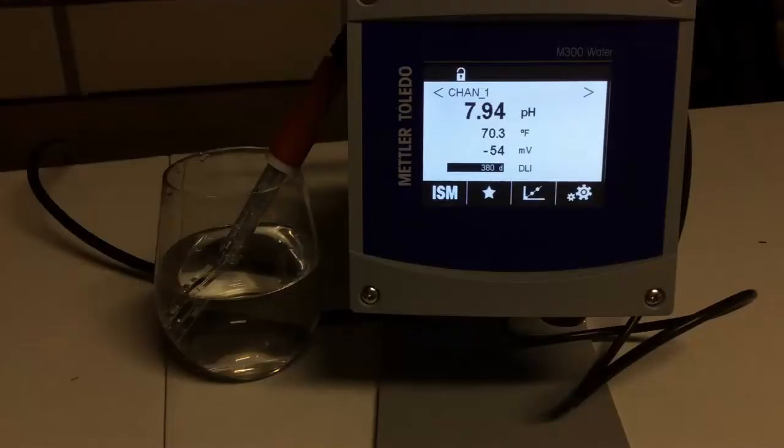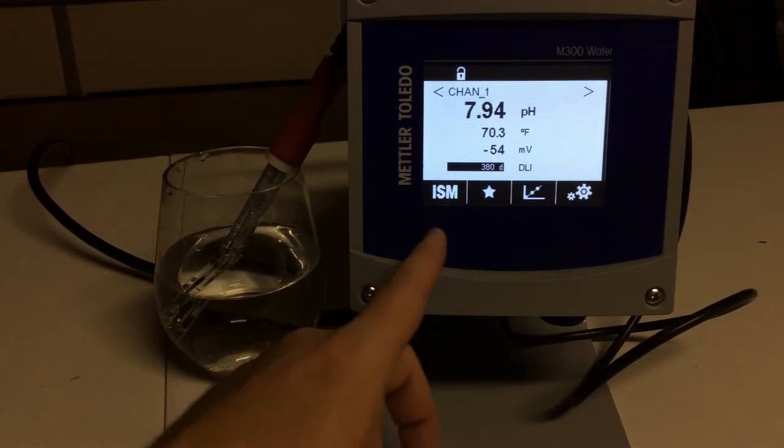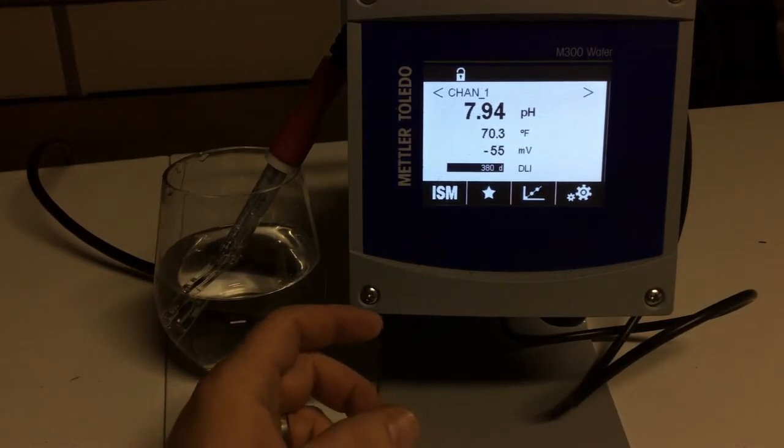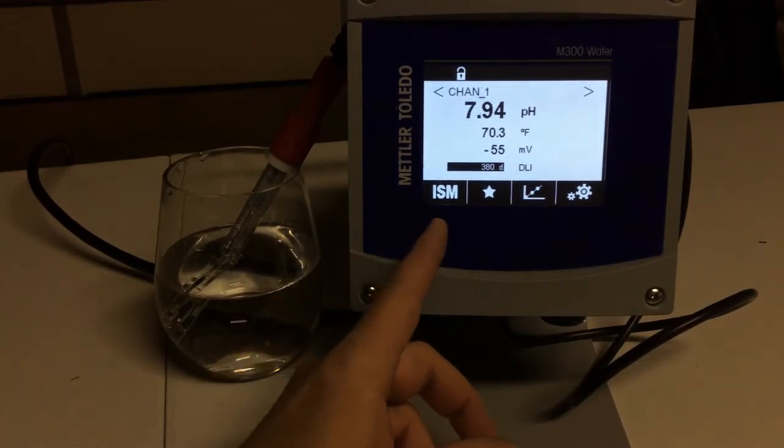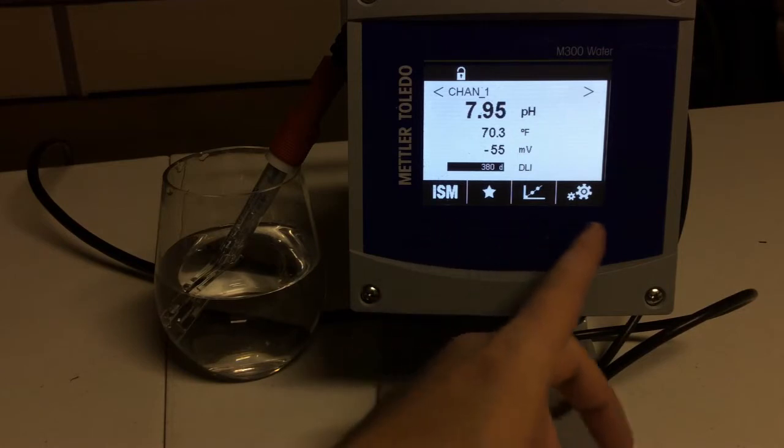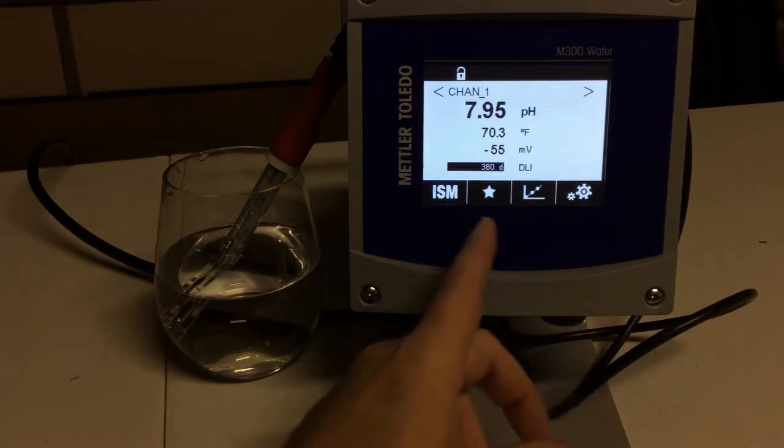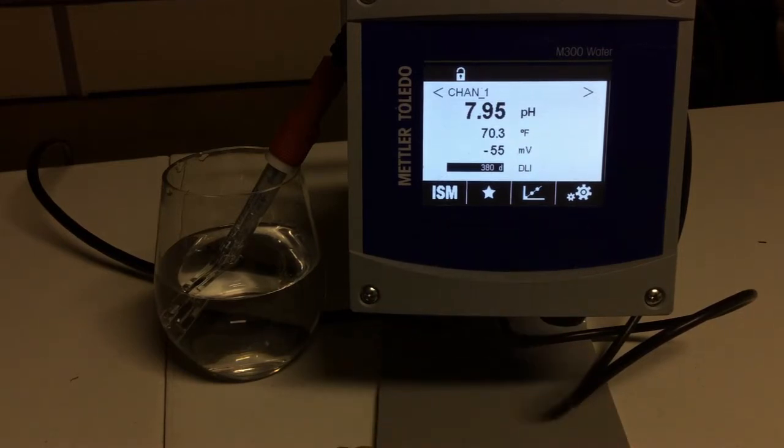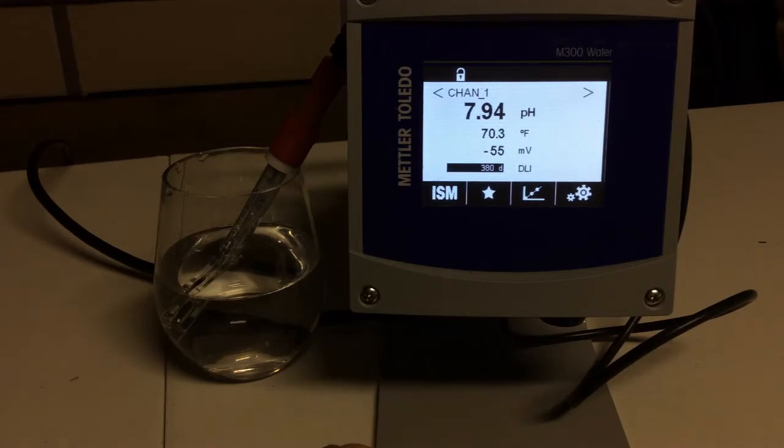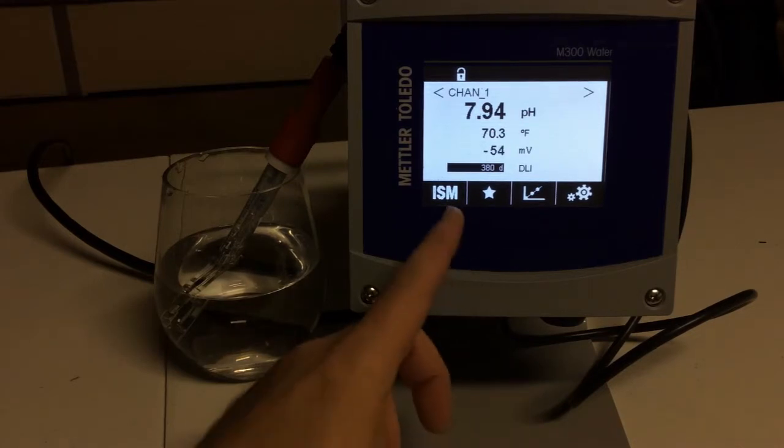As we go through this, I will take you through all the functions, how you set it up, the different ways you can calibrate it to monitor your sensors. The last thing to mention with this, it can do both a digital and an analog sensor, and the key is a digital sensor with Mettler Toledo with their ISM technology. So now I'm going to walk you through some of the basics of the M300 transmitter. It is a touchscreen, and so here are the four function buttons that we can use to navigate through the transmitter to help us get information, calibrate, or whatever you might need.